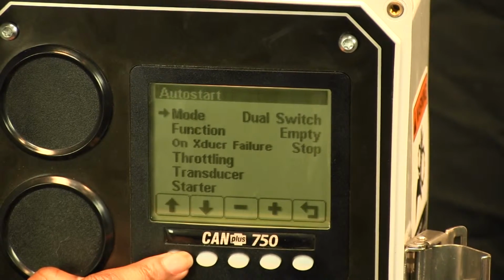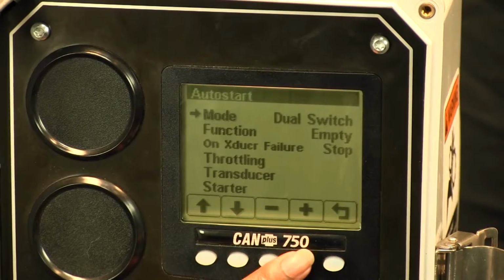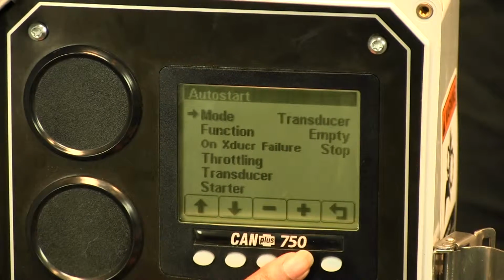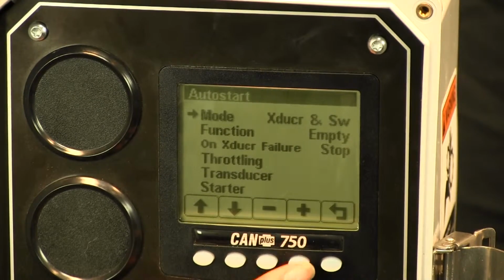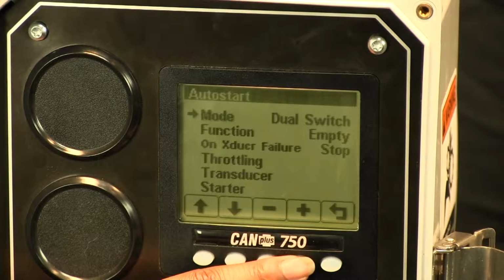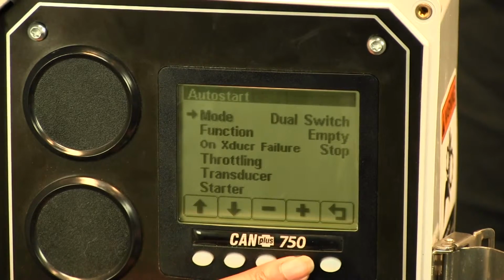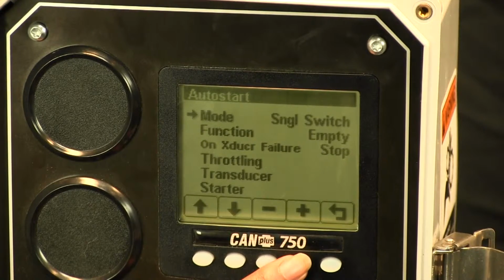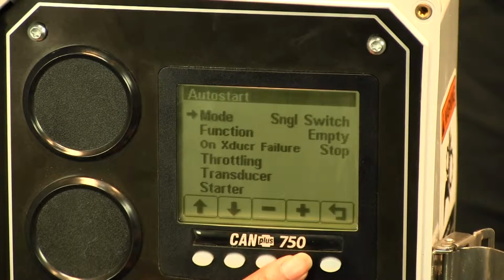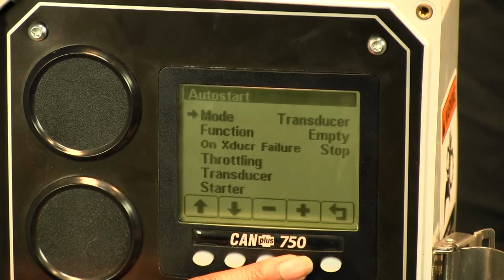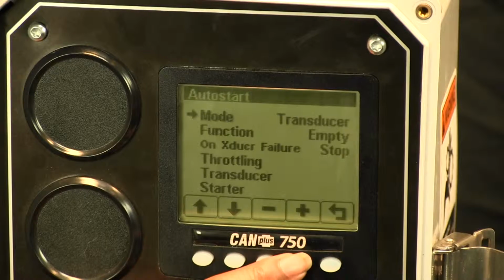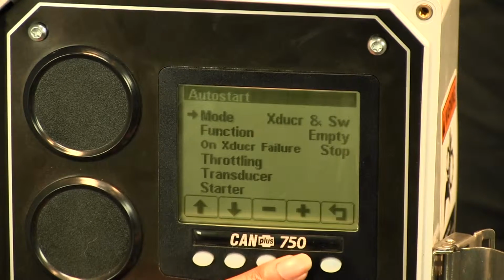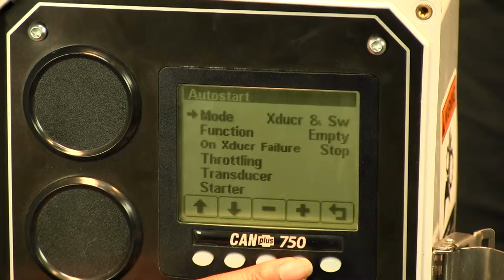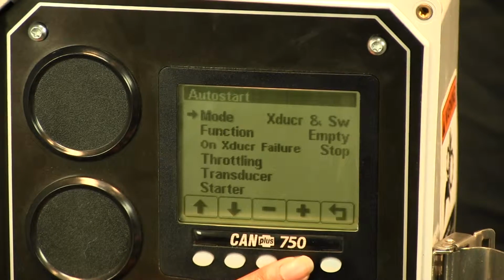So let's just go over some of the different modes that we have available. There's dual switch, single switch, transducer, and transducer with backup floats. When using a dual switch, that's when you're using either two switches or two floats in order to create an auto start event. In single switch, you use one single switch or one float. And then transducer uses an analog input with a 4 to 20 milliamp signal in order to start an event. And the transducer with backup switches is basically the same thing as a transducer setup, but if the start event occurs using just the floats, then the panel is just going to pay attention to the floats until the transducer comes back online.